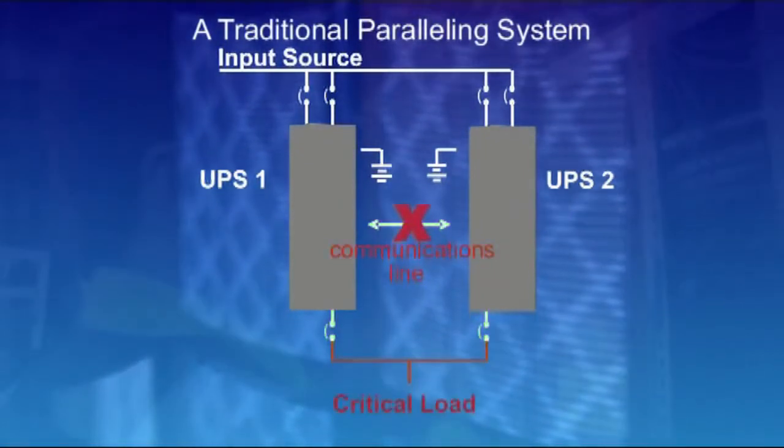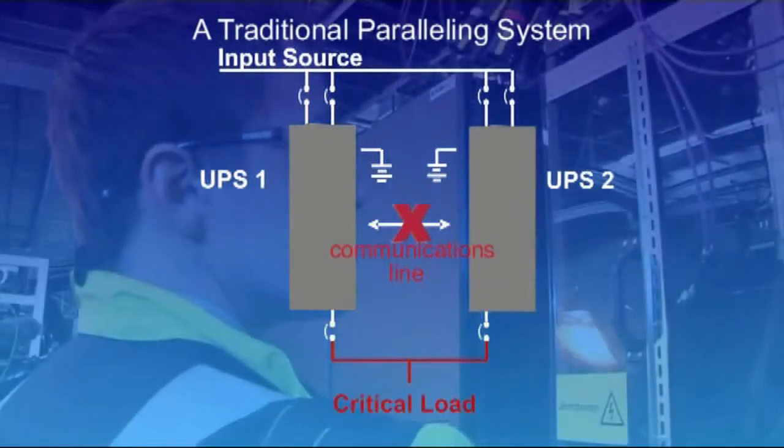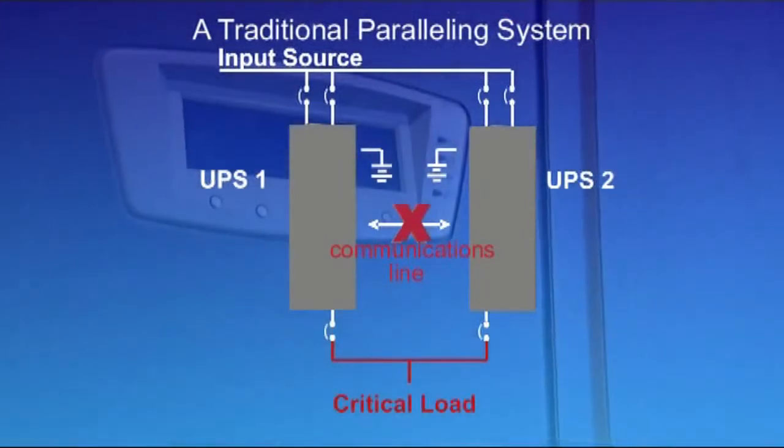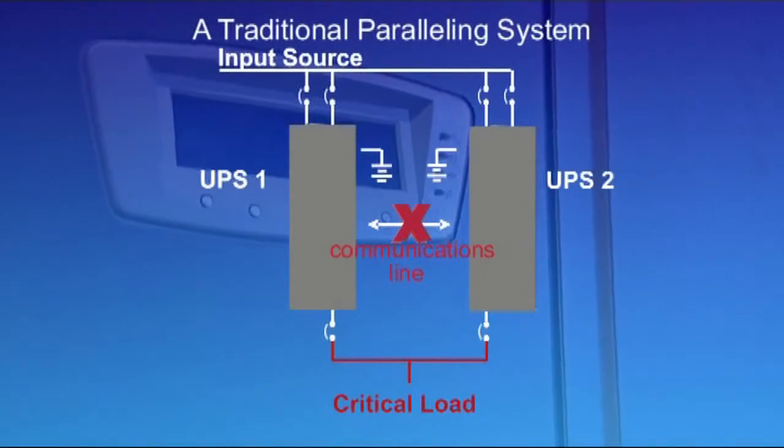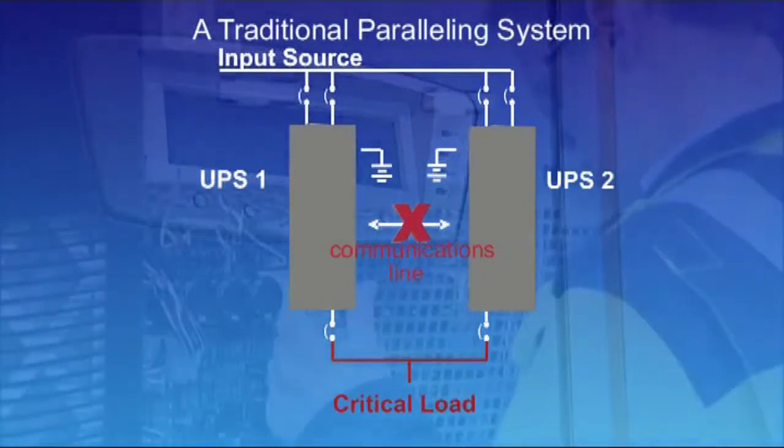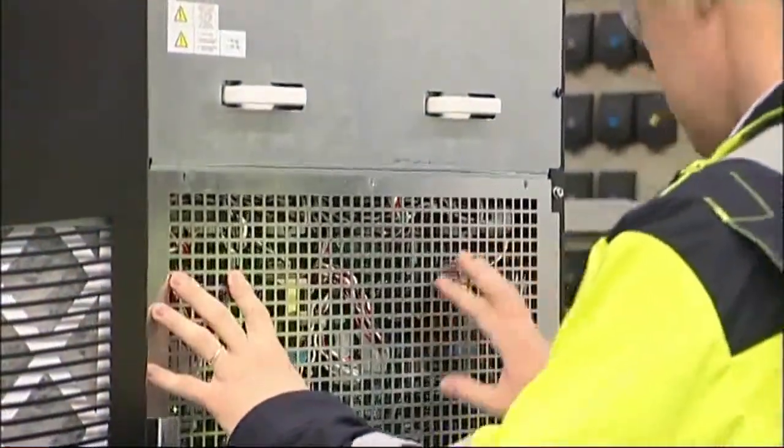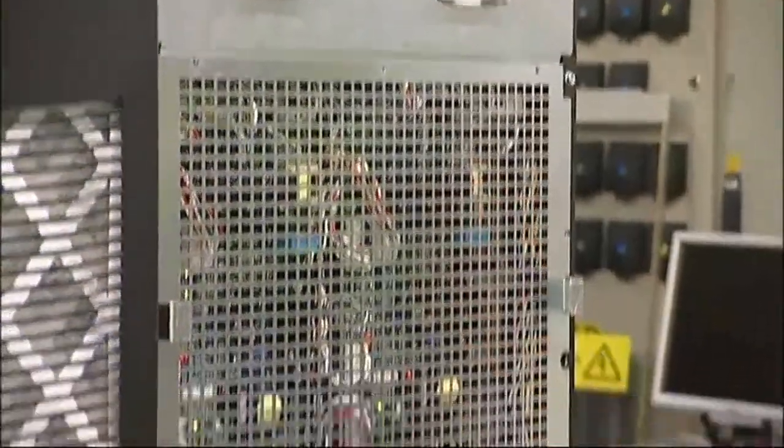In the case of a signal being lost, UPS outputs lose their synchronization, which drives the modules to an imbalanced load share. In this case, a single point of failure in most cases ultimately causes an unwanted system shutdown and potential downtime to critical load.